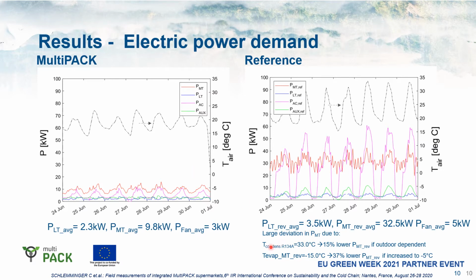What is important to note is that the reference system is running at a constant condensing temperature for the R134a system, which is 33 degrees Celsius, while by adding an outdoor-dependent condensing temperature, we could already save 15% of the electric energy consumption. What was also noticed is that the evaporation temperature of the MT side was rather low. In this case, it was minus 15 degrees C. So here is definitely also an improvement potential. However, this implicates, of course, that the evaporators, meaning the cooling furniture, are designed in a proper way.